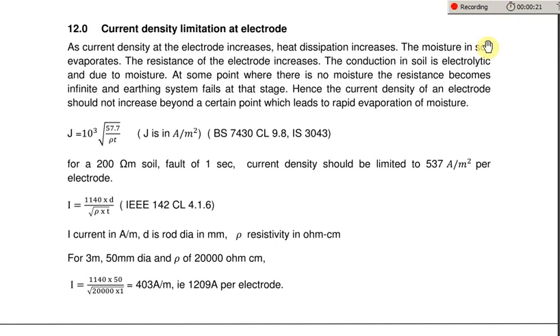The temperature at the electrode increases. As the temperature around the electrode increases, the soil around it starts evaporating the moisture content. We all know that the conduction in the soil is mainly due to the moisture content, because this conduction is electrolytic conduction.